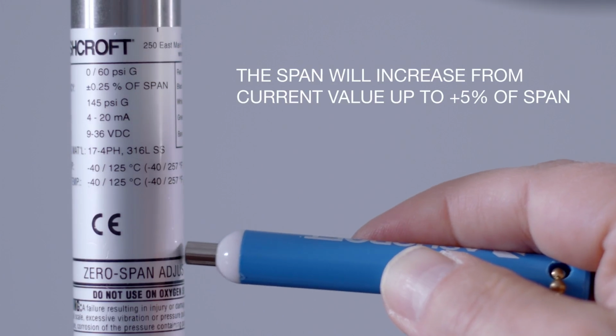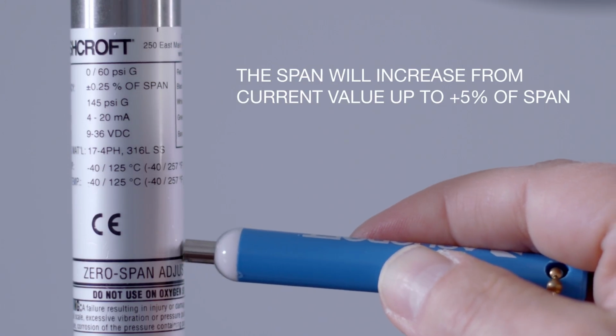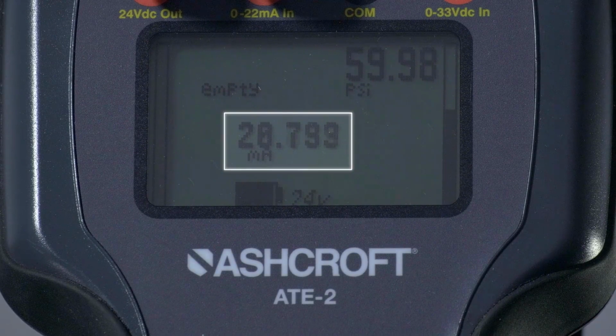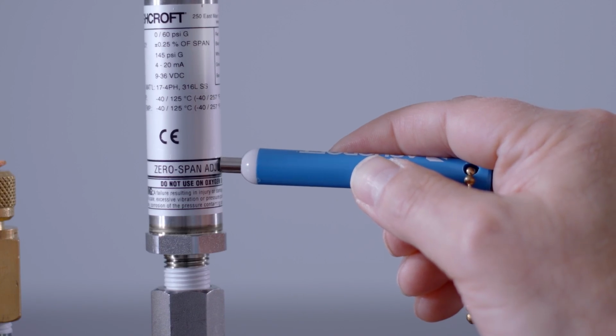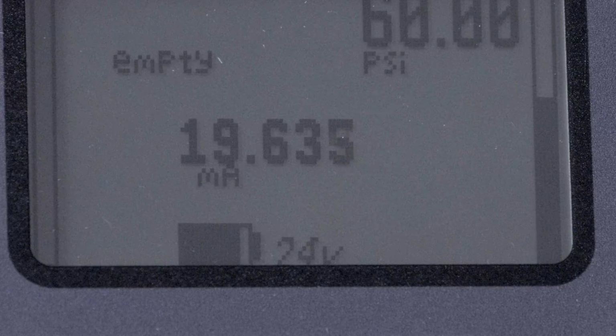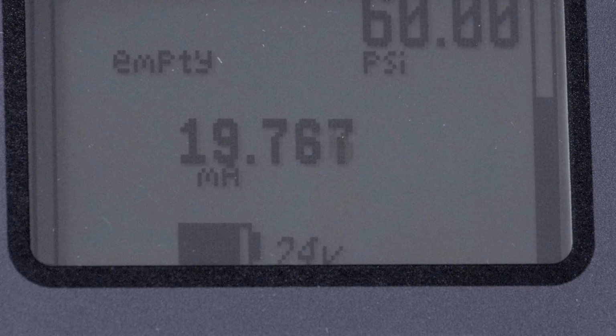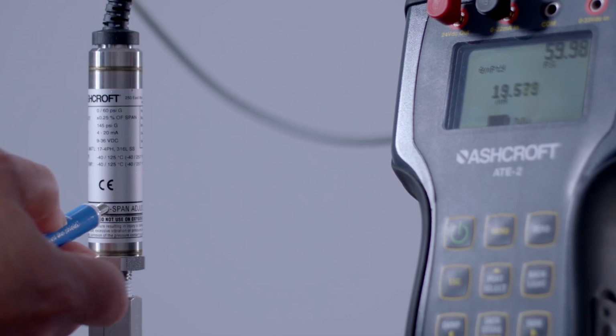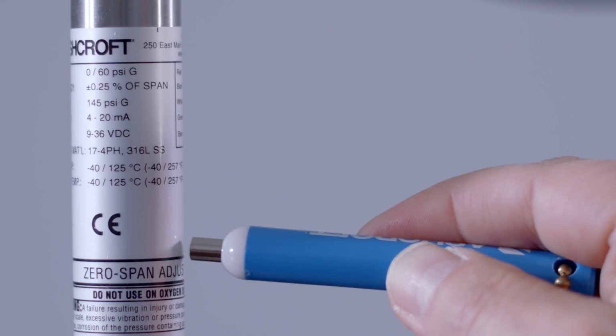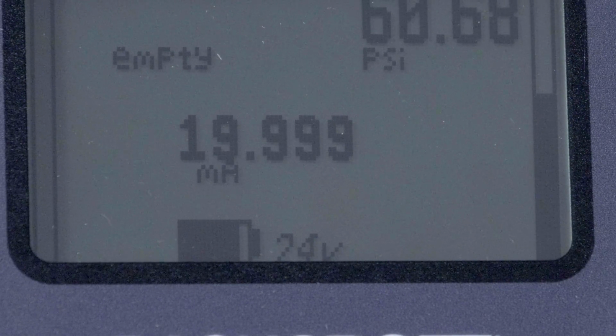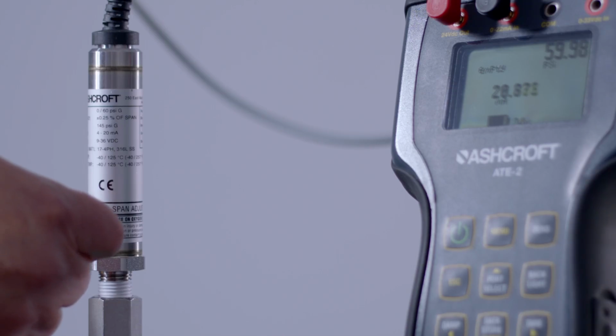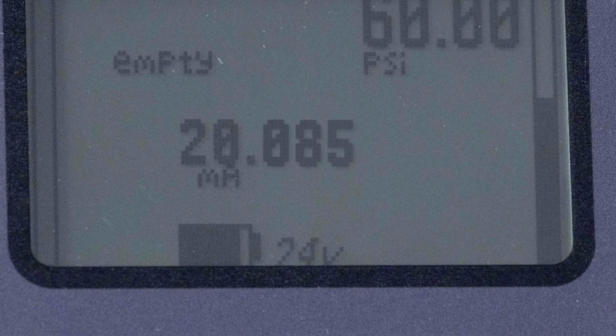The span will increase from its current value up to plus 5% of span. Once the output has reached the max value, the span will jump to minus 5% and continue to increase towards plus 5%. Holding the magnet in position while adjusting the span will increase the speed at which the span value increases. Once you get close to your desired setting, you should tap the magnet against the unit for finer adjustment. If you scroll past the desired value, repeat until you've reached your span value. We have reached our desired value.